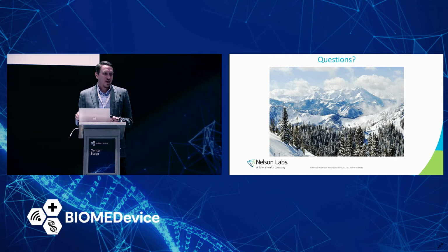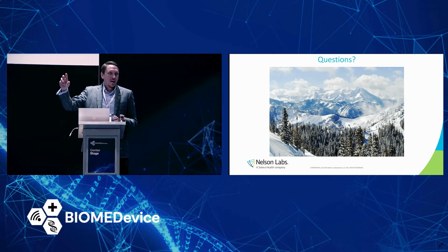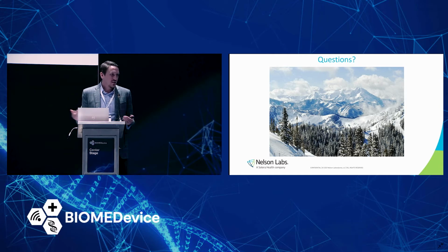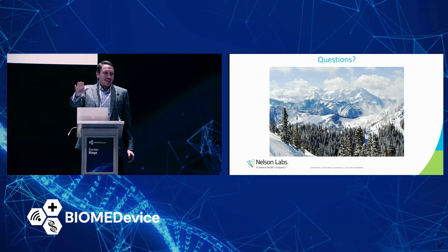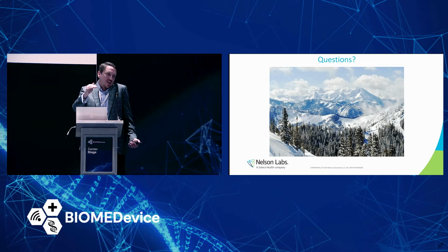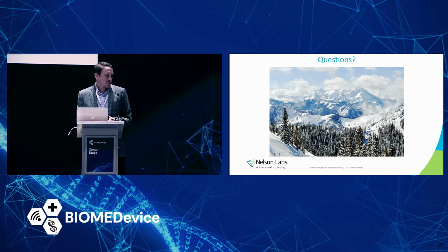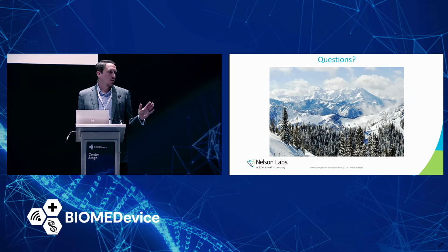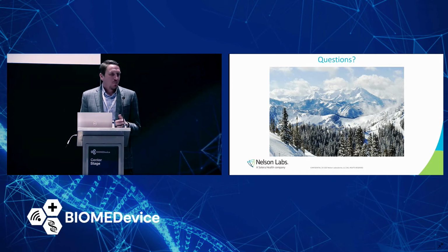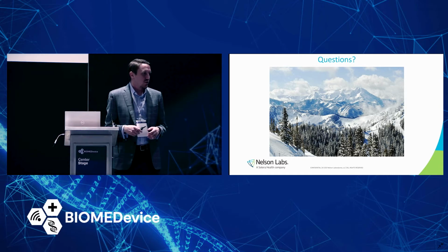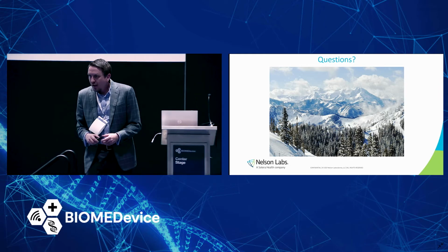Now, let's say that you're making a small change, and you might not submit. A common change would be that your upstream supplier for a polymer is changing one of their suppliers, right? So it's still the same polymer, still like Tecothane, but Tecothane's maker has an upstream supplier change. The question is, does that change matter? Will that affect the biocompatibility of our device? And so then we would call that a biological risk assessment, where we say, okay, here's what happened. Is there a risk? Well, yeah, there's a potential risk to this change. Does that matter or not? Does the biocompatibility of the device change? So that type of thing. It's a lot more common with a change assessment. But you can interchange them a little bit, for sure. Any other questions? Yeah. Here, I'll bring the microphone over.